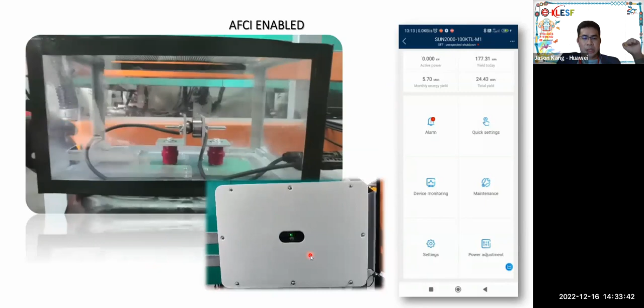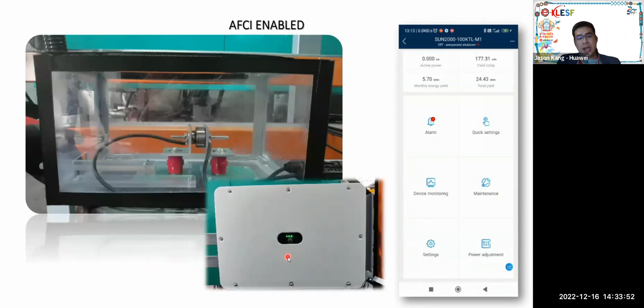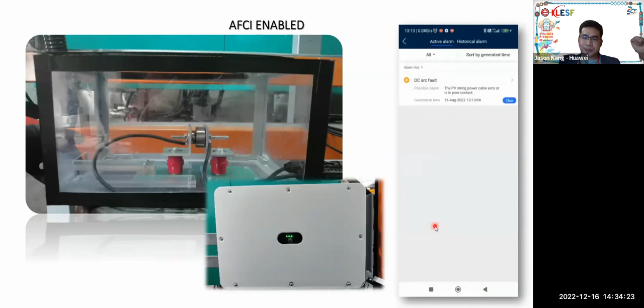So this is when AFCI is enabled. Very quick one. There's an arc and the inverter directly trips. Yeah. As I mentioned, it can be tripped in less than 0.5 seconds, lah. And of course, for the accuracy of the detection, we actually utilize our AI to do this. Okay, so you also have your alarm in your management system, and from the alarm we actually can tell there's a DC arc fault. And not only that, from the alarm you can also tell which string the fault comes from. Yeah, so if you take a look at this, when you click into this DC arc fault alarm, you can see that on PV string number 2 there's an arc fault, so we can tell up to the level of the string. Yeah.